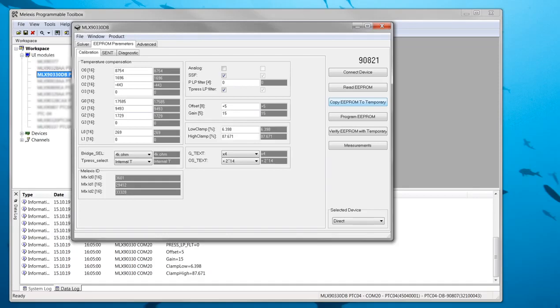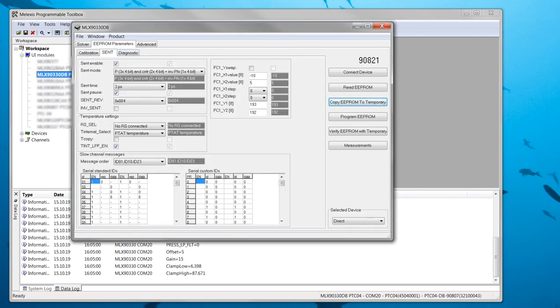To change the messages in the slow channel, I go to the SENT tab of the E²ROM parameters. The grid on the bottom left configures the slow channel messages from the SENT standard. Here I disable ID01 from the normal sequence by setting a 0 in the EN column and set a repetition factor in the REP column. A value of 1 corresponds to transmitting the diagnostic every other message. The value in the left EN, REP and data columns will be written to E²ROM, while the right EN, REP and data columns contain the values that were already programmed in the E²ROM.